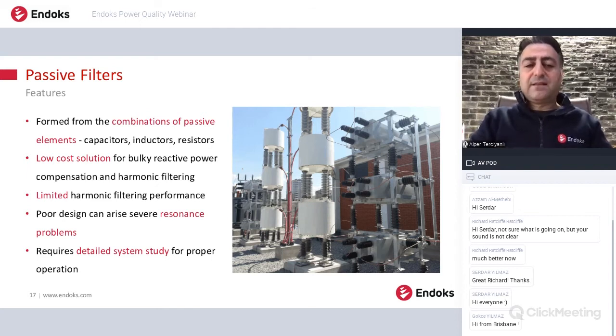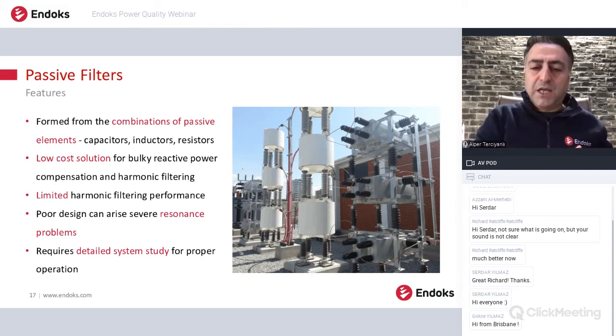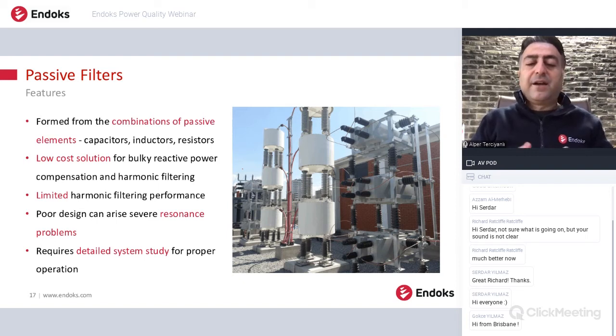But these passive filters have limited harmonic filtering performance because it's passive equipment with a fixed frequency curve. If the frequency changes, the filtering performance of the filter, of course, changes. And a poor design can cause severe resonance problems if you don't design the passive filter in a correct way. You might increase the harmonics in the system. Actually, we put in these passive filters to avoid or eliminate harmonics, but if the design is wrong, you can increase the harmonics, and this is very important.